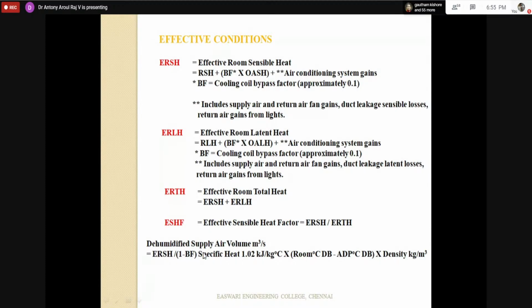What we are doing here is taking the definition of the effective room sensible heat factor. This is one form. If you simplify this, you will get this: the effective room sensible heat is the dehumidified supply CFM multiplied by density multiplied by specific heat, into room dry bulb minus the ADP temperature of the coil. That is the definition. If I want the dehumidified CFM, I bring everything to the other side. That is how we decide the volume flow rate of the AHU for a particular room where we are doing the load calculation.